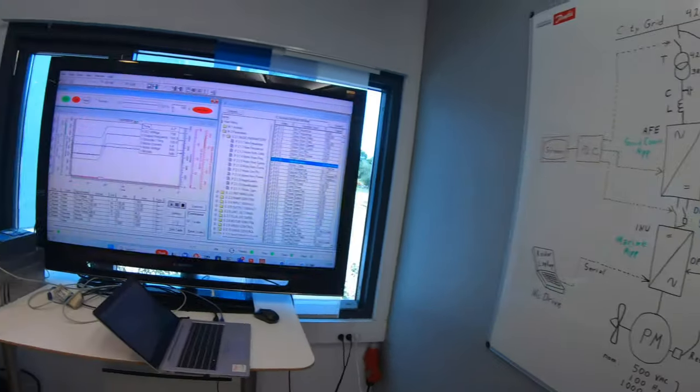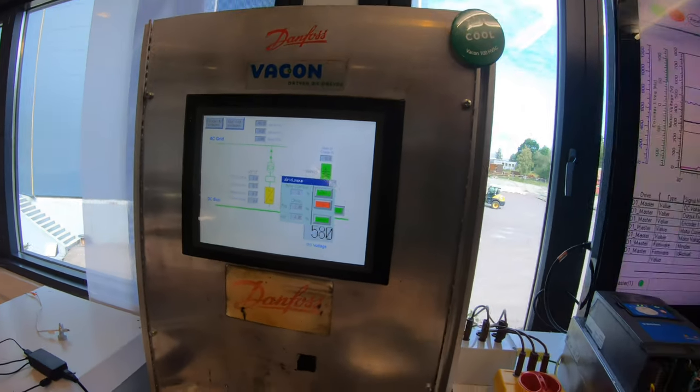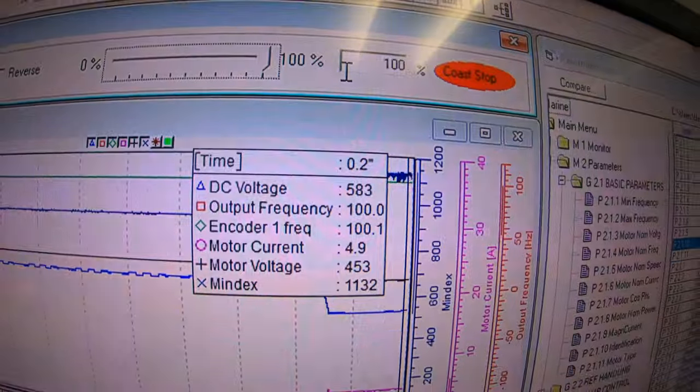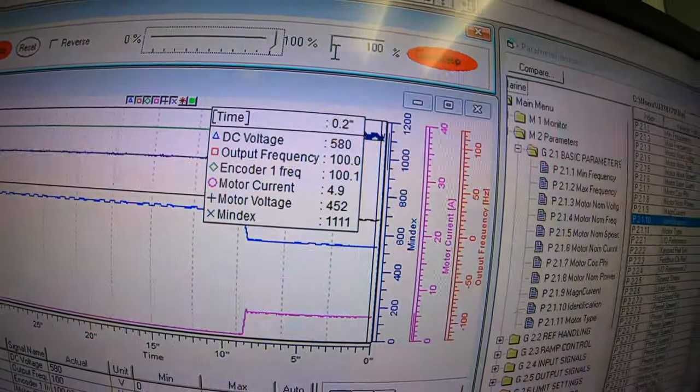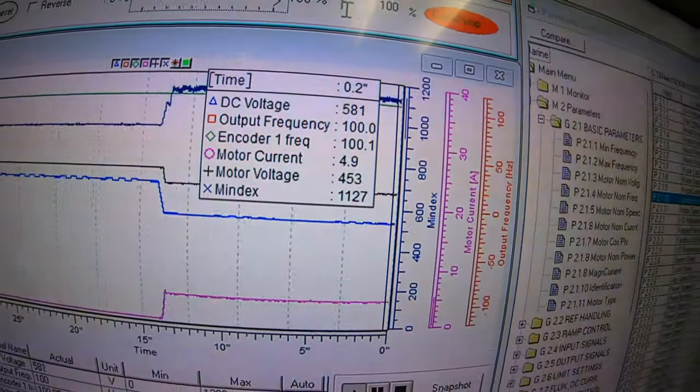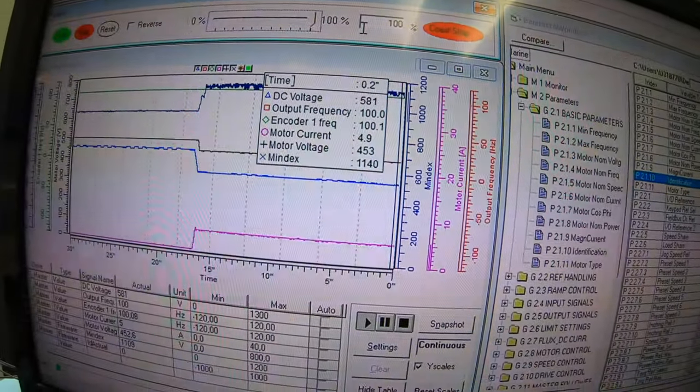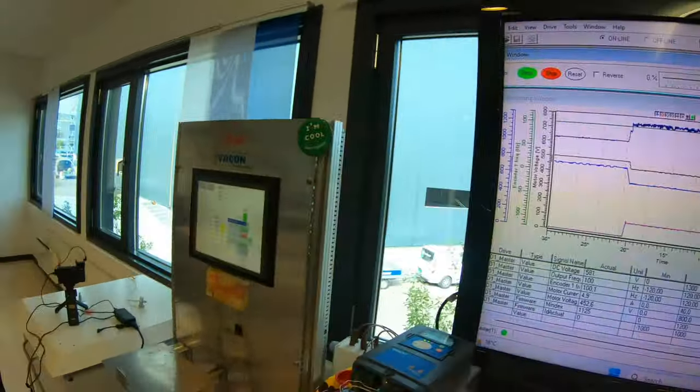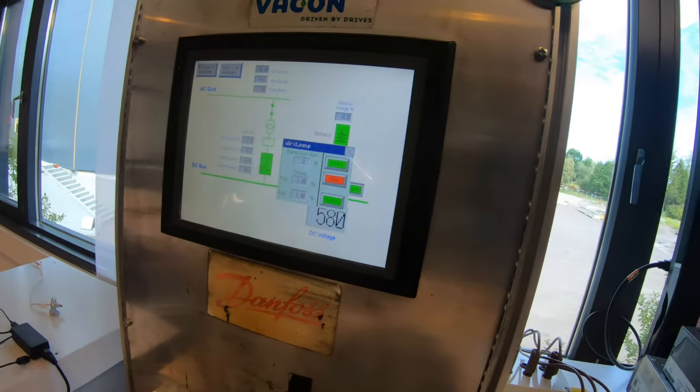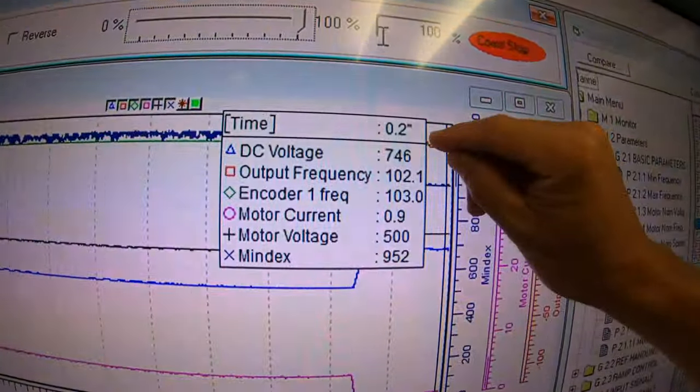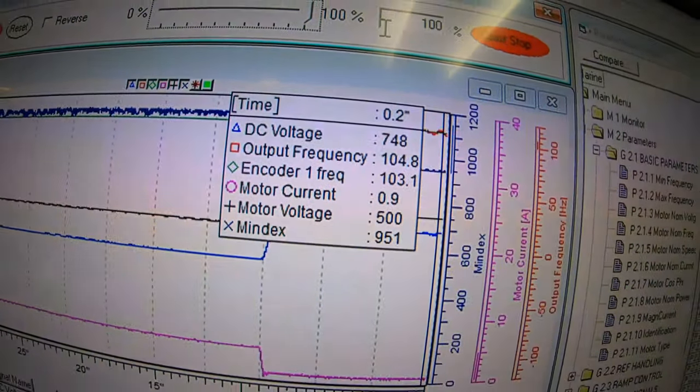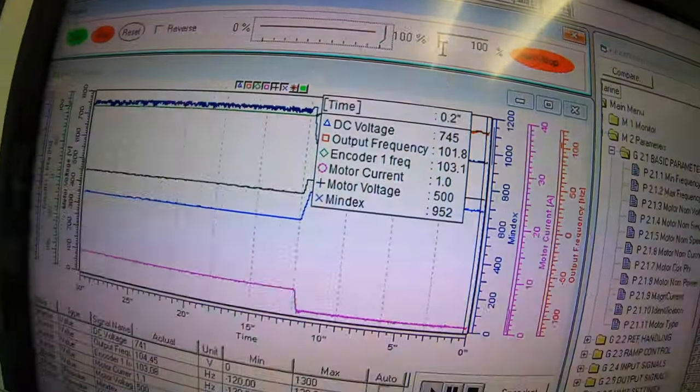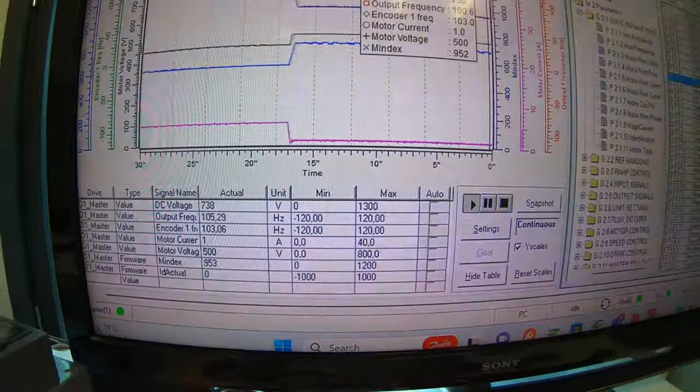What if the DC voltage would not be enough? Let's stop the active front end. It still runs at 100 RPM. The current went up because it is now using the current to suppress the motor voltage. The motor voltage is now 450, and that is a lot less than the 500 volt nominal. So this is not a good situation for tuning the motor. So the DC voltage is quite important to get everything right. You can hear in the motor something change when I increased the voltage, the DC voltage to 740. Now we got the motor voltage of 500 volts. So be aware of the DC voltage before you start any advanced tuning of the motor.